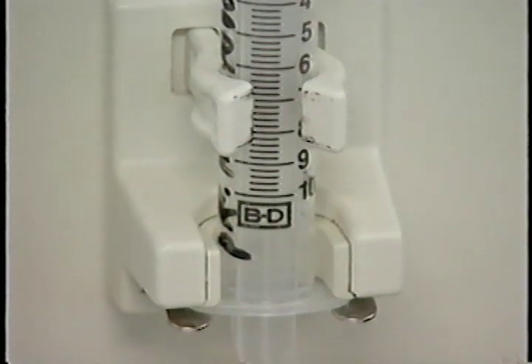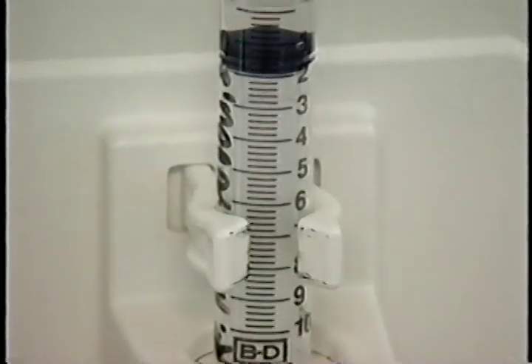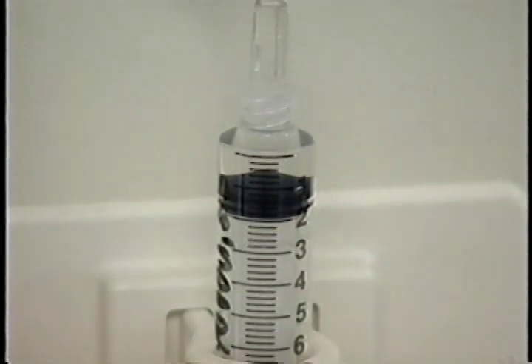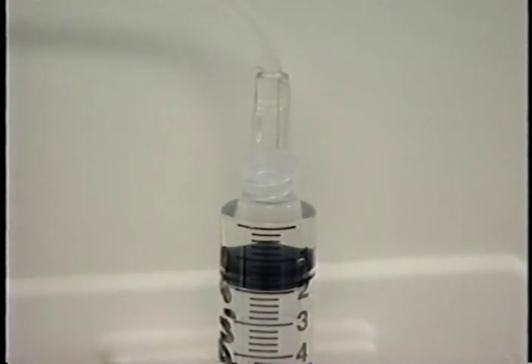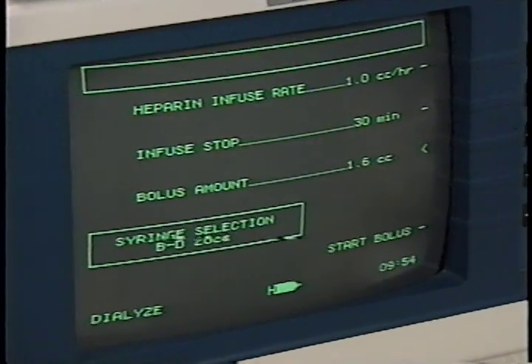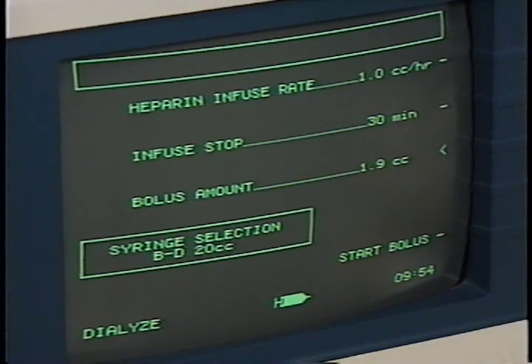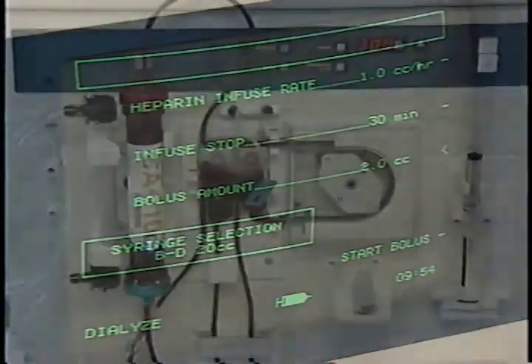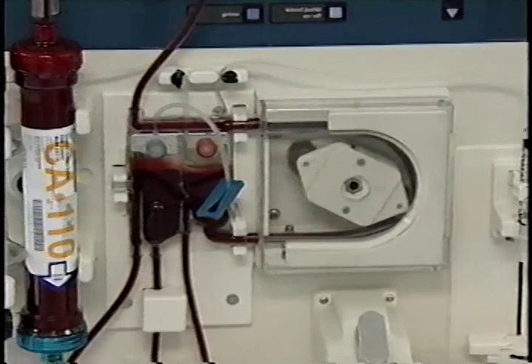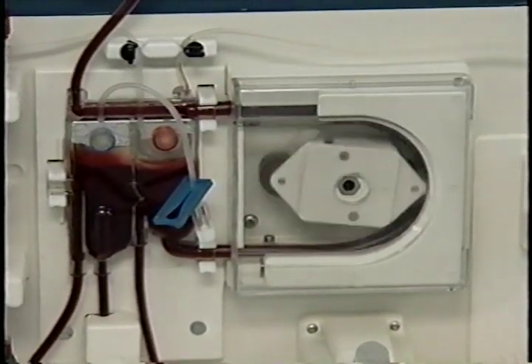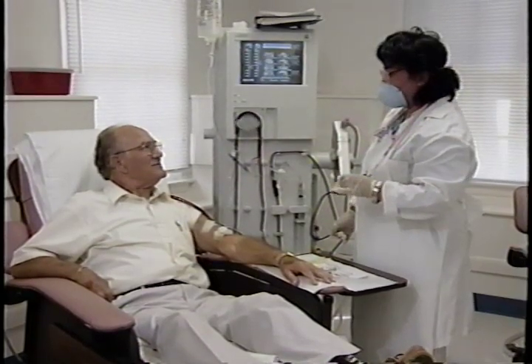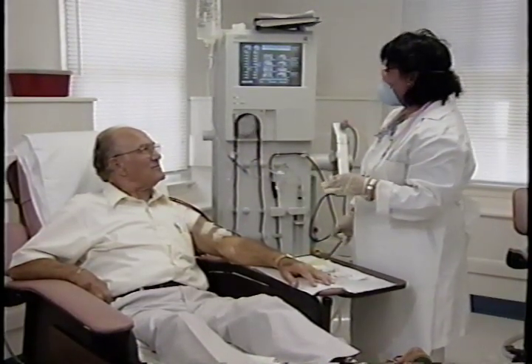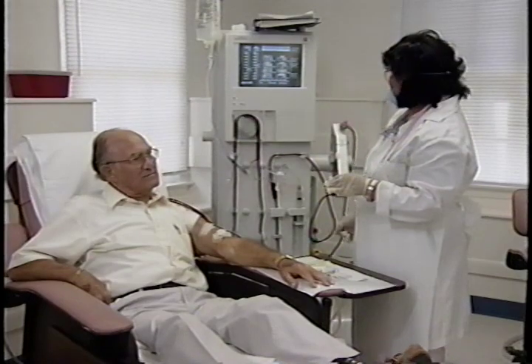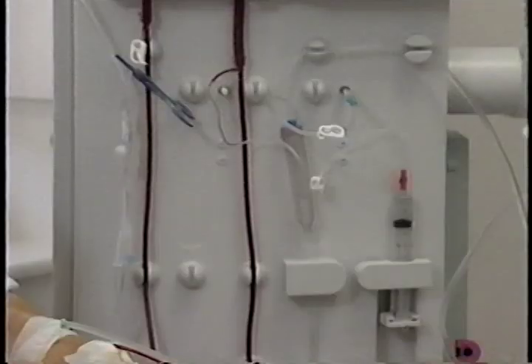Choosing the wrong size syringe, failure to prime the heparin line, or to turn on the heparin pump may cause an improper dose of heparin to be delivered. If there is concern about the dose delivered to the patient, the calibration of the infusion pump should be checked. If your patient suddenly shows unusual clotting characteristics, you should initiate actions to alleviate the problem. Talk to the patient and determine if there have been any unusual medical problems since the last treatment. Patients with an infection or fever often require an increased heparin dose to prevent dialyzer clotting.